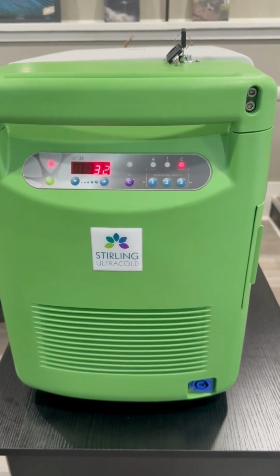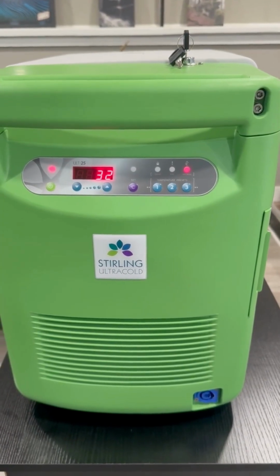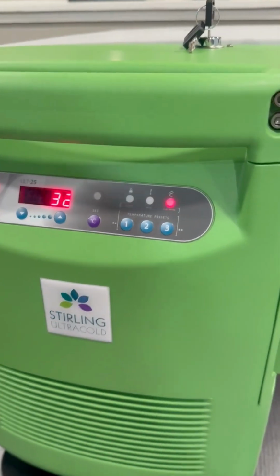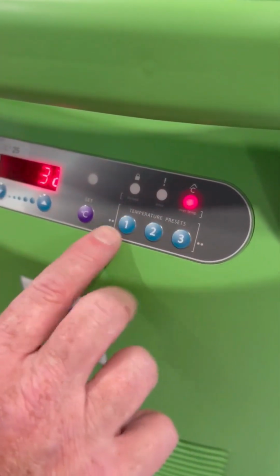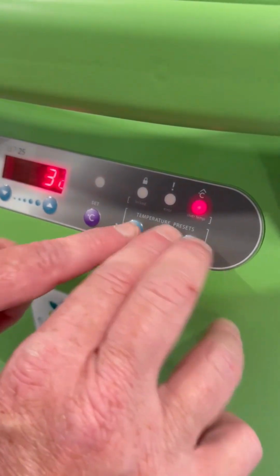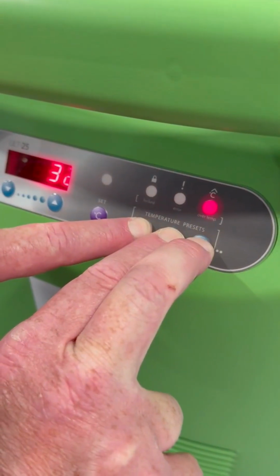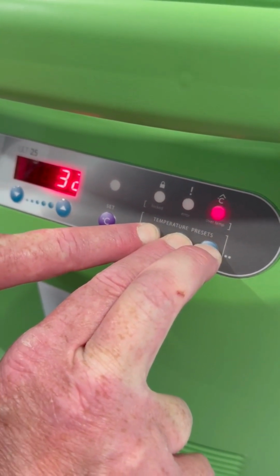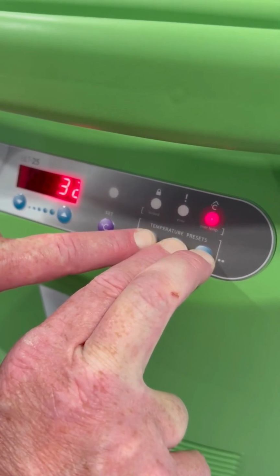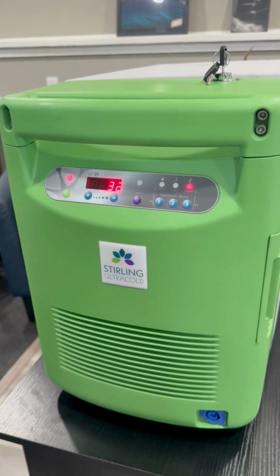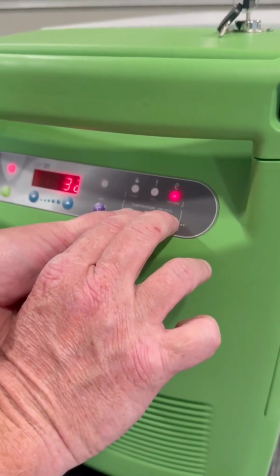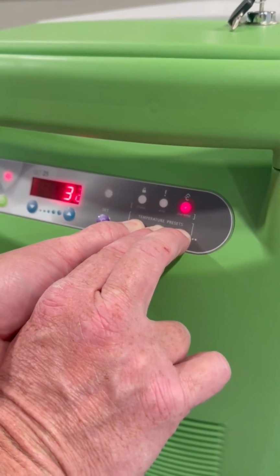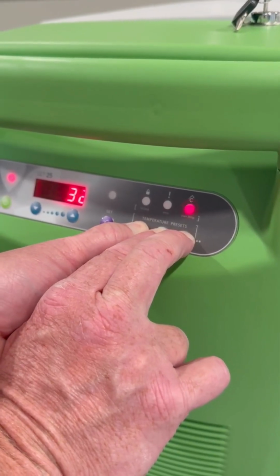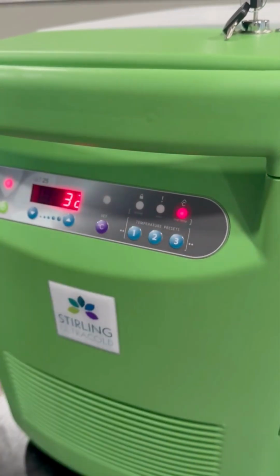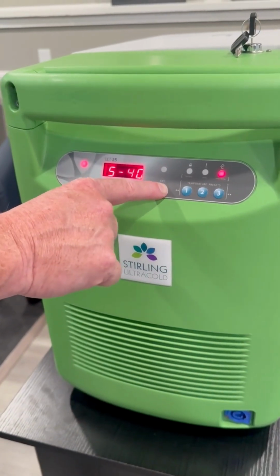Most labs like to have security features, and the ULT25 has a lockable LED screen. In order to lock the LED screen, you are going to press and hold for 5 seconds numbers 1, 2, and 3. Freezer is now locked. In order to unlock the LED panel, press numbers 1, 2, and 3 simultaneously for 5 seconds and it will unlock. Freezer is now unlocked and you can change the temperatures.